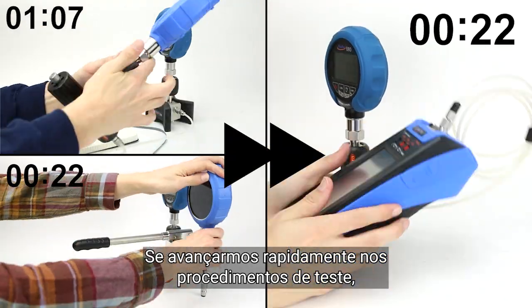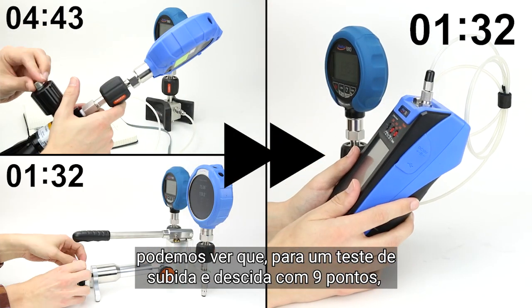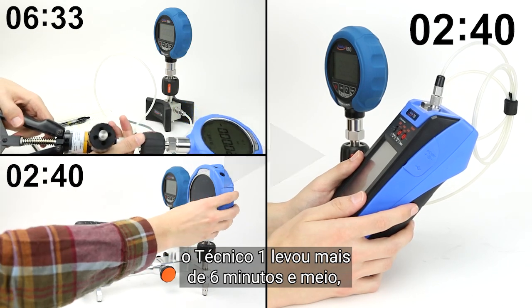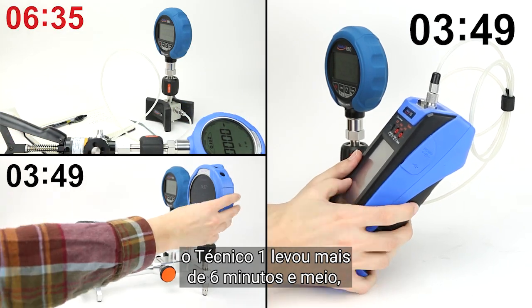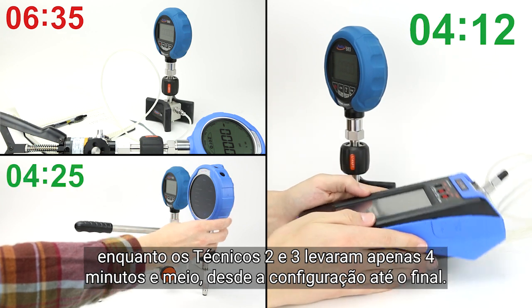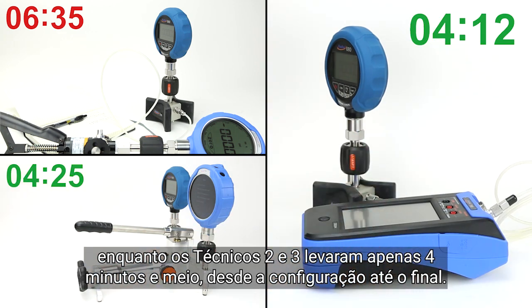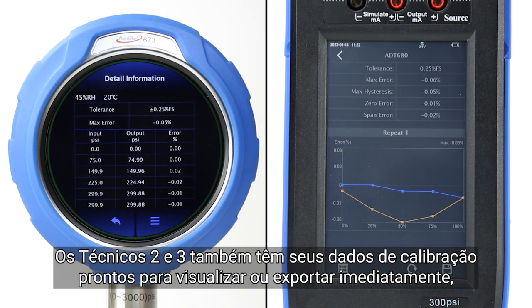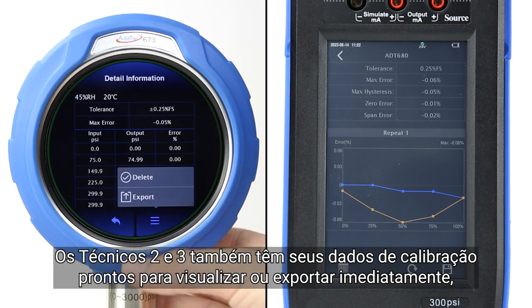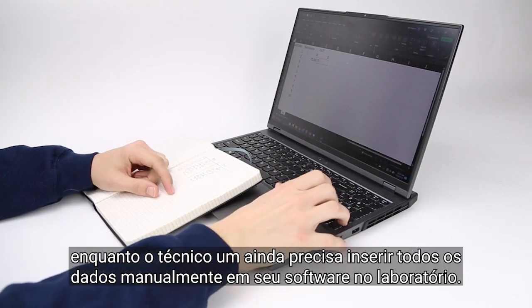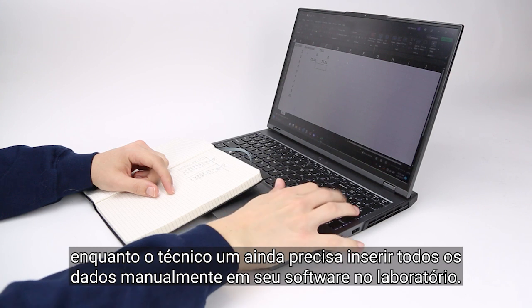If we fast forward the testing procedures, we can see that for a 9-point round-trip test, Technician 1 took over 6.5 minutes, while Technicians 2 and 3 only took 4.5 minutes from setup to finish. Technicians 2 and 3 also have their calibration data ready to view or export immediately, while Technician 1 still has to enter all of their data manually into their lab software.